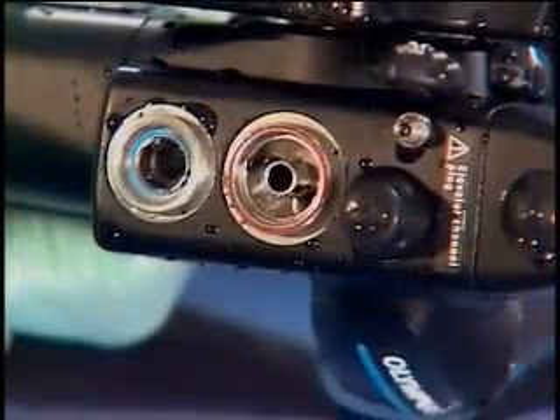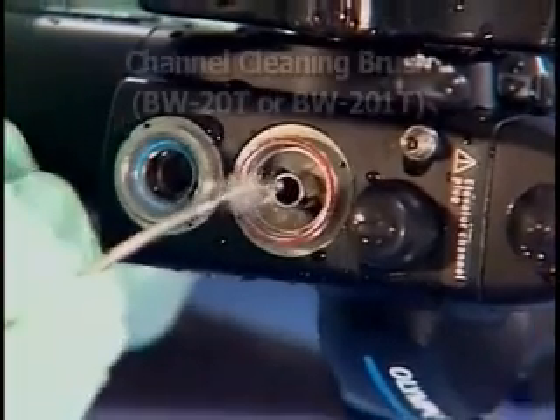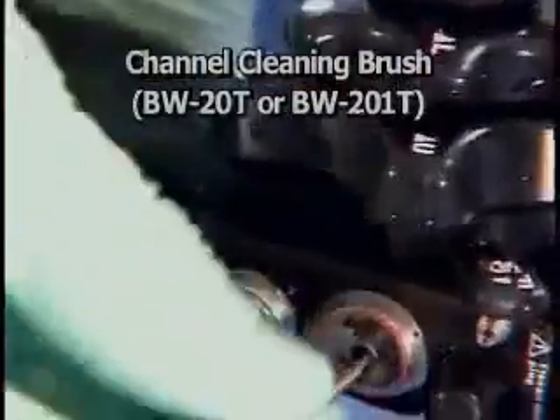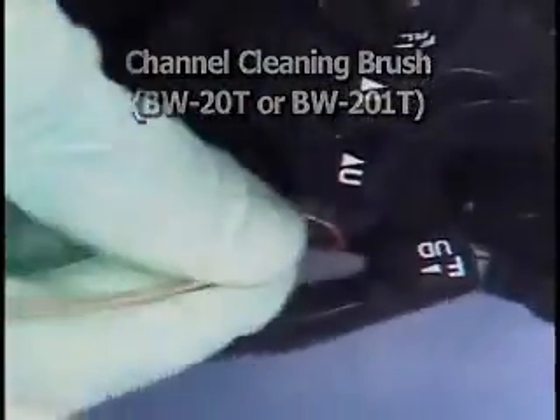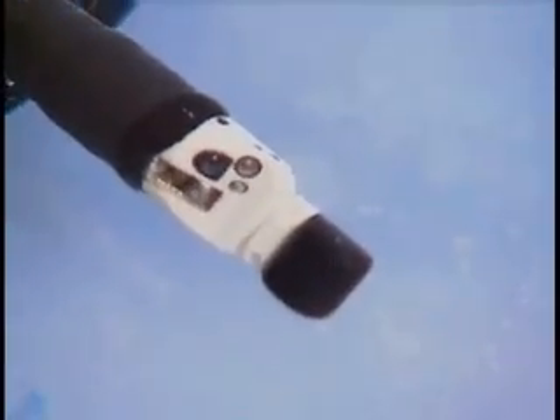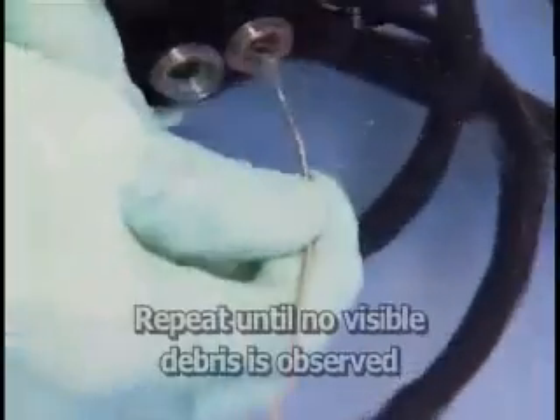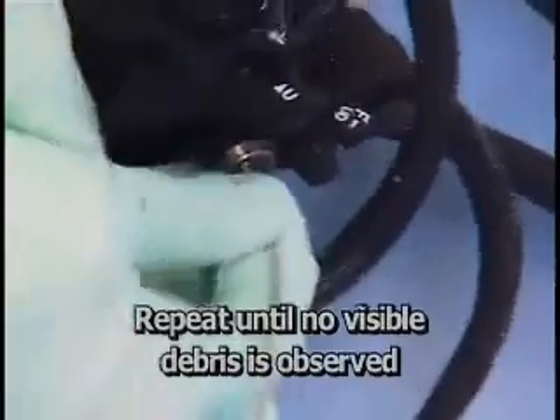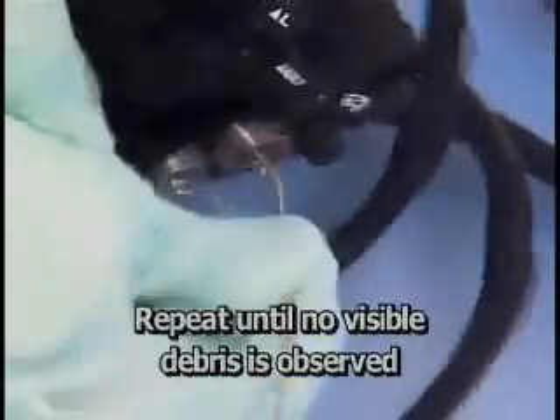To brush the suction channel within the insertion tube, insert the channel cleaning brush into the center opening of the suction cylinder. Use short strokes to advance the brush through the insertion tube until it emerges from the distal tip. Remove any debris from the bristles with your fingers and gently pull the brush back through the channel. Inspect and clean the bristles again. Repeat this process until you cannot see any further debris on the bristles.